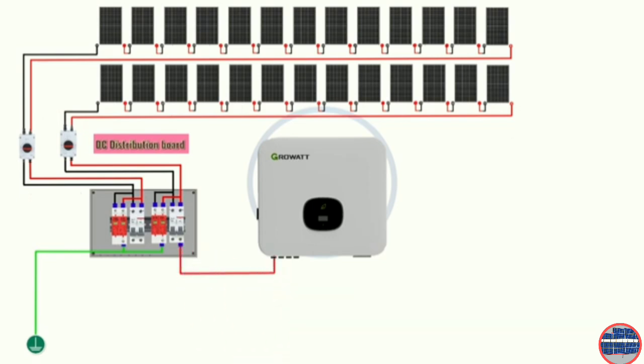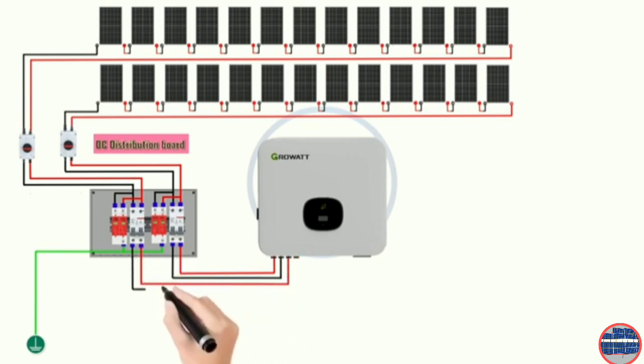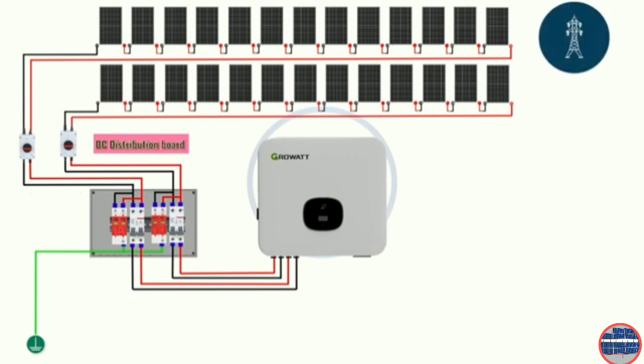MCB output to inverter. Connect the positive output of the MCB to the positive PV input of the solar inverter. Connect the negative output of the MCB to the negative PV input of the solar inverter. Important considerations. Polarity: DC systems are polarity sensitive. It's crucial to connect the positive and negative wires correctly. Reversed polarity can damage equipment. Double check all connections.